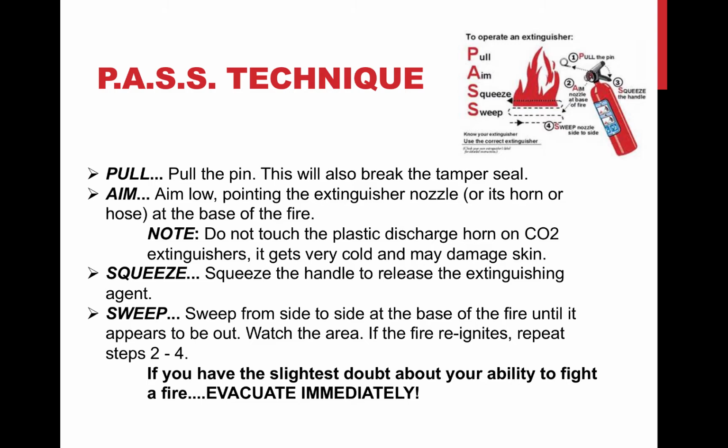Pull the pin. This will break the tamper seal. Aim low, pointing the fire extinguisher nozzle at the base of the fire. Do not touch the plastic discharge horn on the CO2 extinguishers. It gets very cold and you can actually give yourself freeze burn. Squeeze the handle to release the extinguishing agent. Sweep from side to side at the base of the fire until it appears to be out.